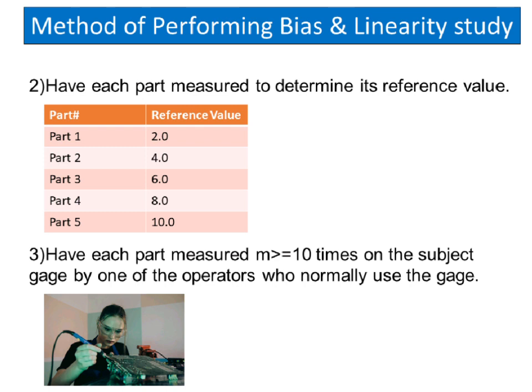Step 3: Have each part measured M greater than or equals 10 times on the subject gauge by one of the operators who normally use the gauge. One operator should perform all the measurements.